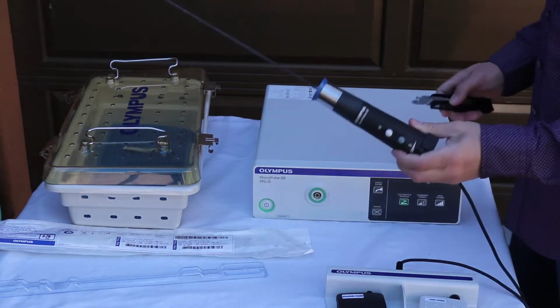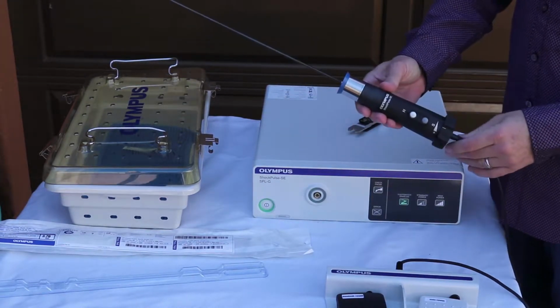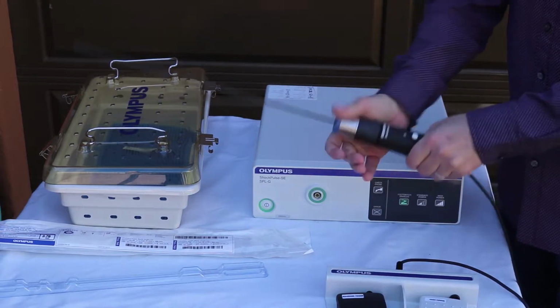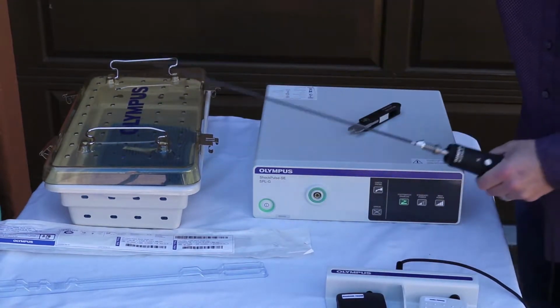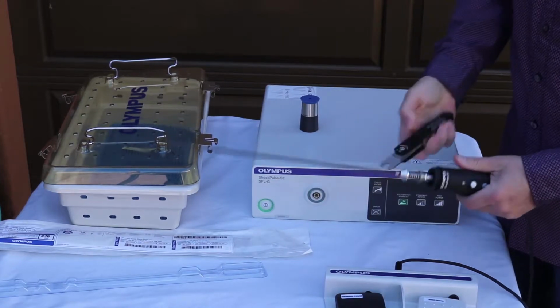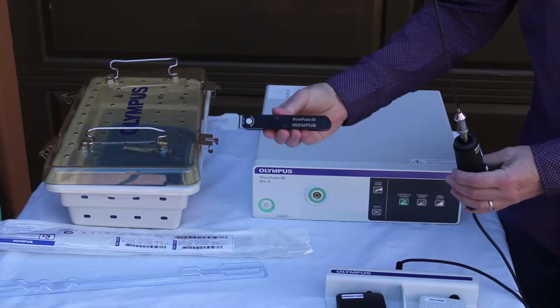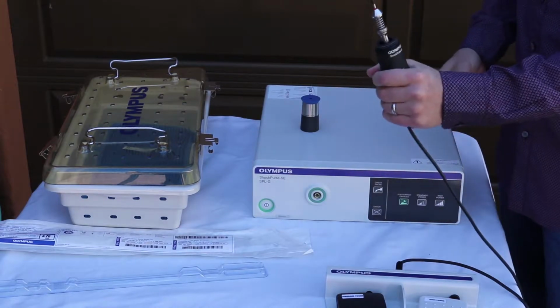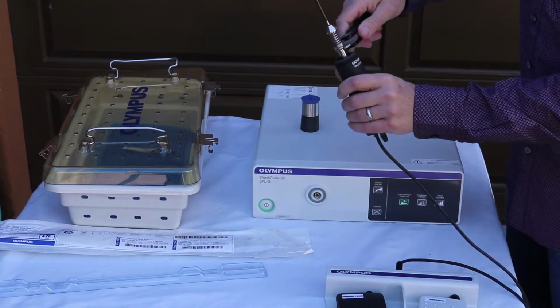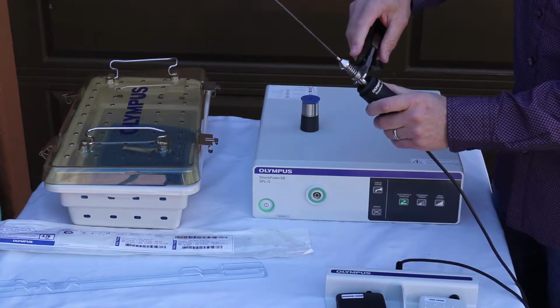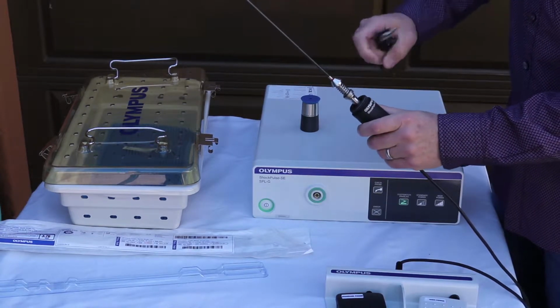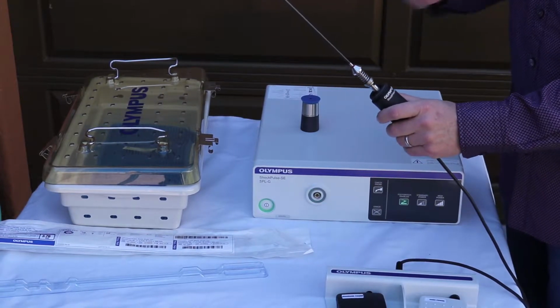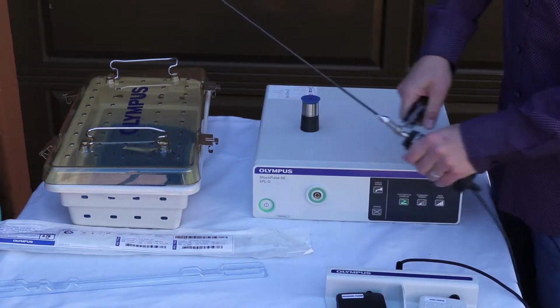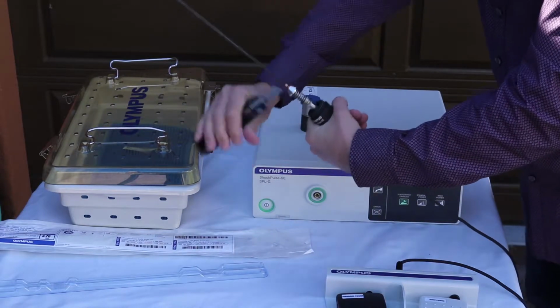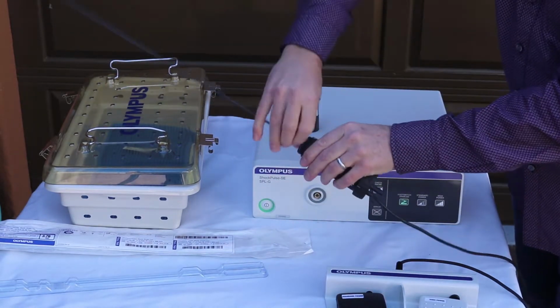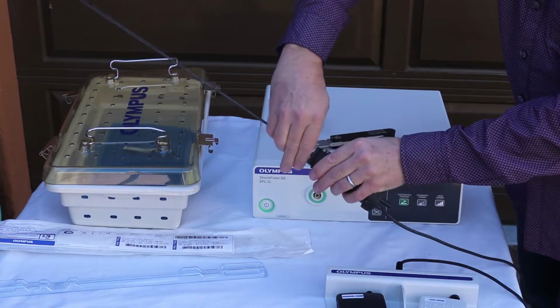The other thing I should mention is takedown or cleanup of the device when the case is finished. You just take the nose cone off, and then you want to use the same wrench that you used to torque it on, and I'd hold it the same way. You want the label, the Olympus label, up, and you hold the transducer like this. One thing I should mention is after prolonged use, this probe can get cranked on there pretty tight. It gets torqued on, so you may have to really work at it to get it off. But basically you just loosen it up, you'll feel it give, and then you can unscrew it with your fingers like this.